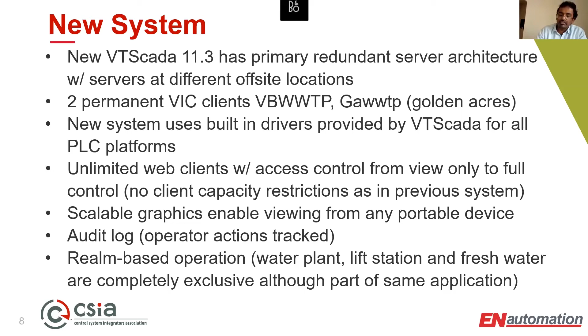You've got freshwater sites, wastewater treatment plants, and lift stations, and the personnel or operators are different for these different groups. That's where VT SCADA's realm-based area filtering allowed us to set up the application so that when a wastewater treatment plant operator logged in, all they saw was information related to wastewater treatment plants and nothing else. This included graphical interfaces, alarming, historical data points available for trend, and even audible alarms where, if an alarm at the water plant goes off, that client will hear it. So realm-based area filtering was a massive feature that helped this application.